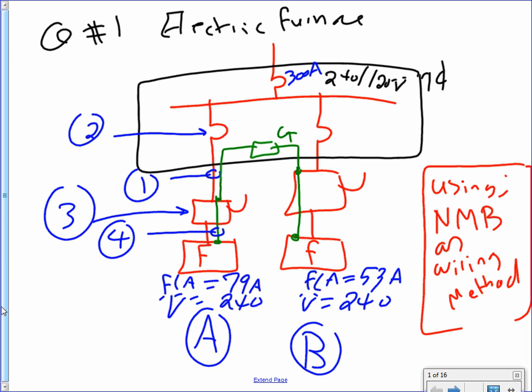Okay, here's what we have. We have a 240/120 single phase panel. I don't care what the amp is, but 300 amp, and I have two electric furnaces fed from this panel. Of course there will be other things. These two electric furnaces both have full load amps: 79 for the first one, at 240 volts, and for the second one, full load amp is 53, voltage is 240. It's furnace A, furnace B.